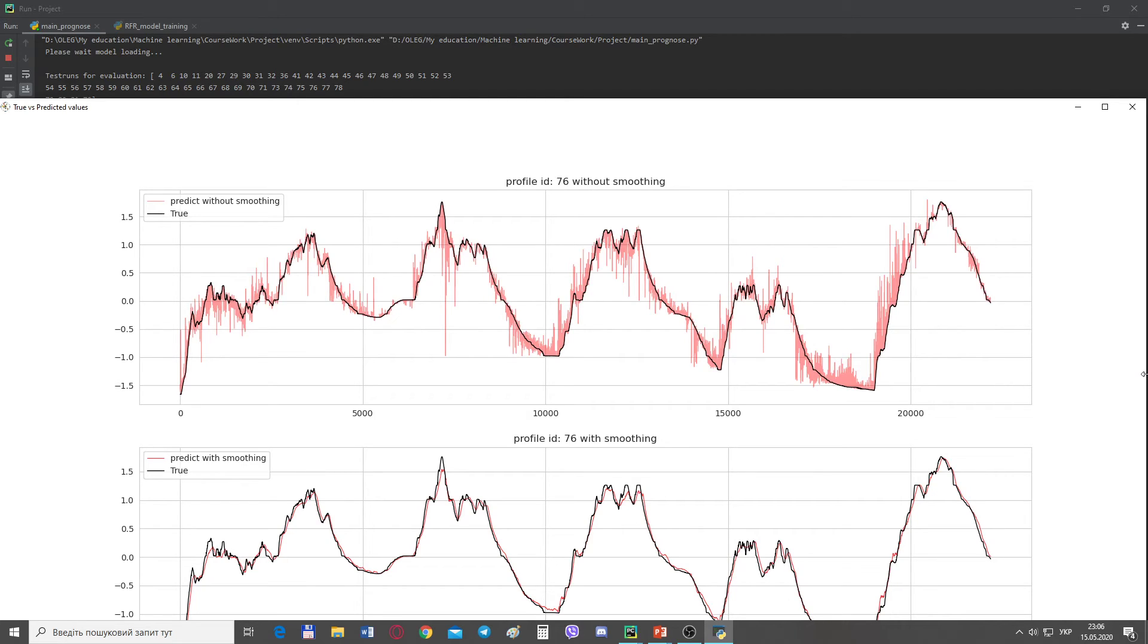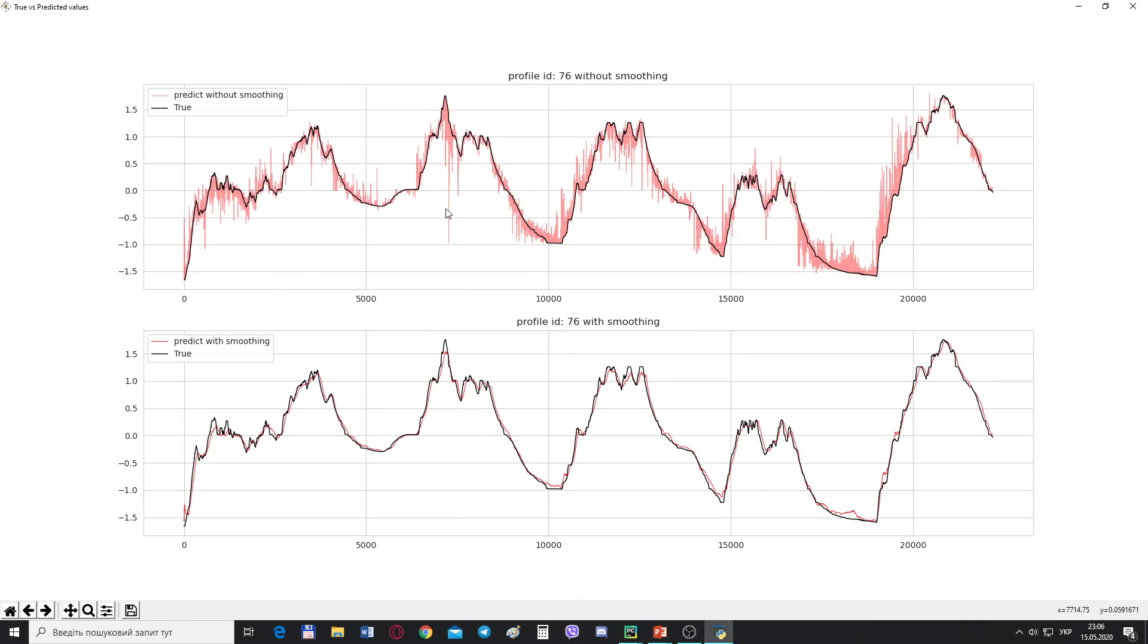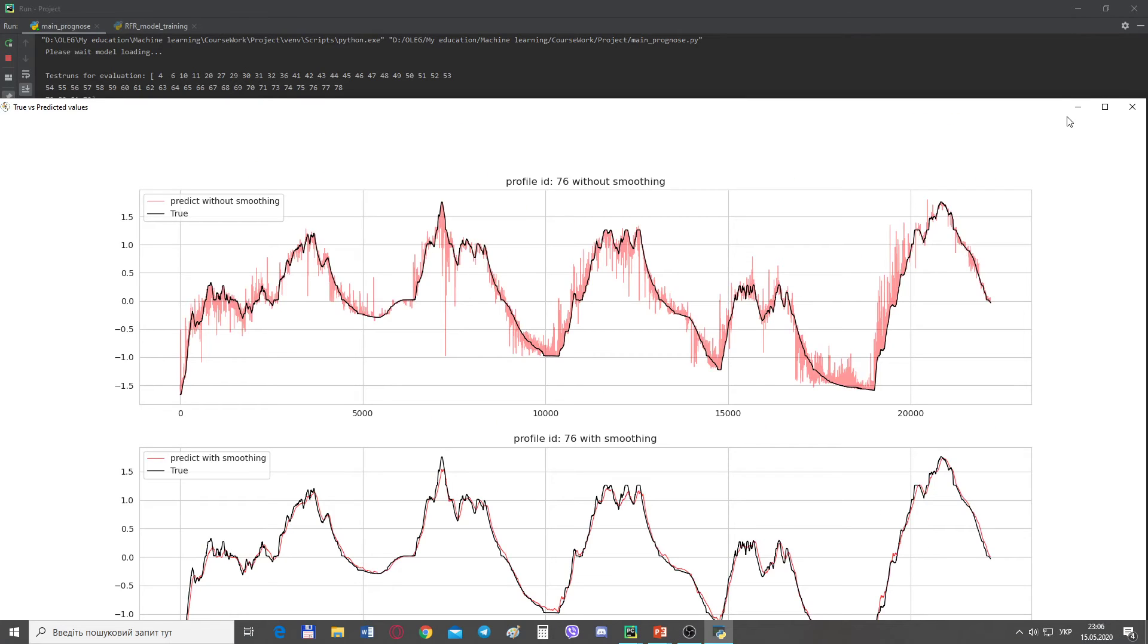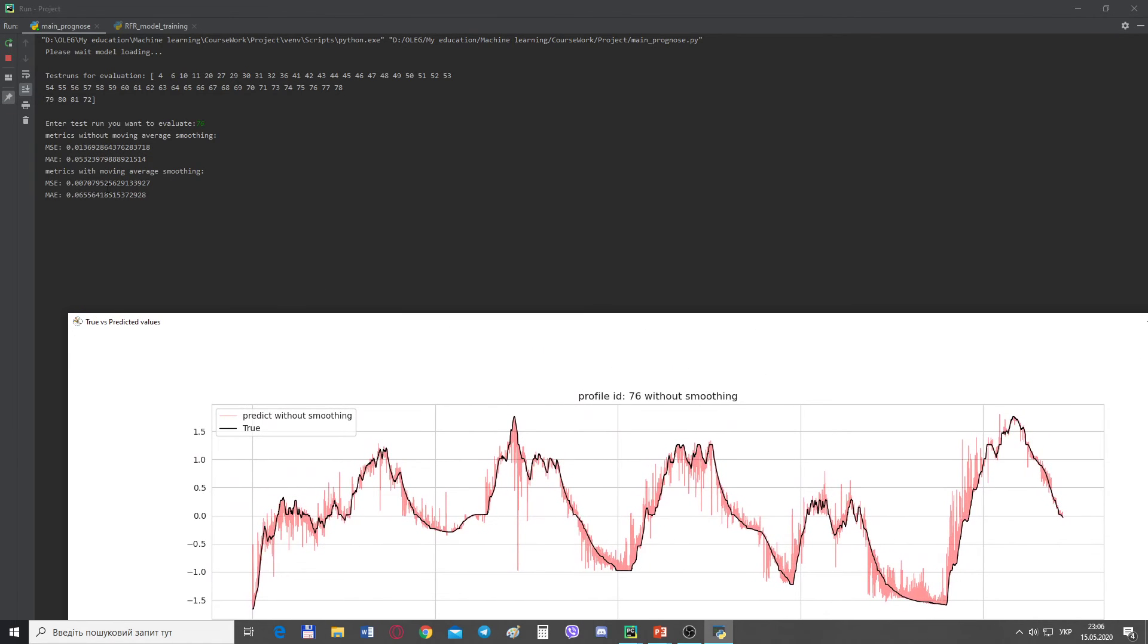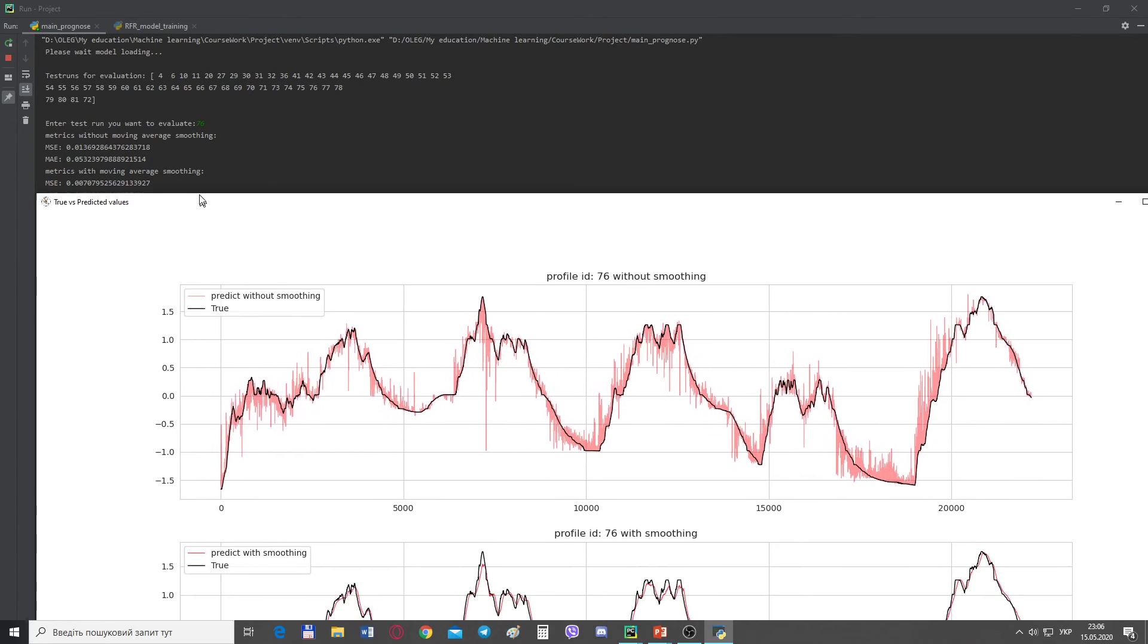Especially when the true signal shows a lot of variation. To filter out the noise generated by the model, applying a moving average function, which we can see on the bottom graph. Combined with the moving average function, the random forest regressor gives us a fairly accurate prediction of the stator winding temperature. The moving average has reduced the noise in the predicted output values and has had a positive impact on the MSE for this specific test run. Now, MSE we can see here. It's MSE without smoothing, without moving average. And this is MSE with smoothing average.